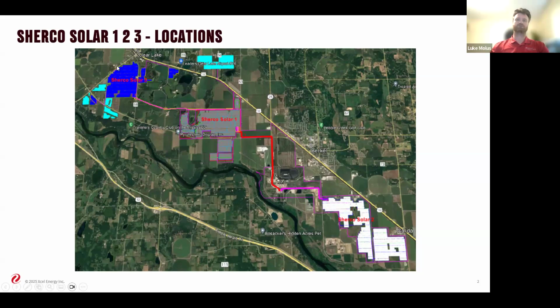Sherco Solar 3 is a little more broken up than Sherco Solar 1 and 2, but it feeds the same way. Its tie back to the substation runs underground, following this pink line, and ties into the substation we call Sherco Solar West. So Sherco Solar 3 doesn't have its own substation on site; it's tied into the Sherco Solar 1 substation, with the Sherco Solar 2 substation up in this corner. We tie both of those substations back into the Sherburne County generating facilities generation switchyard.